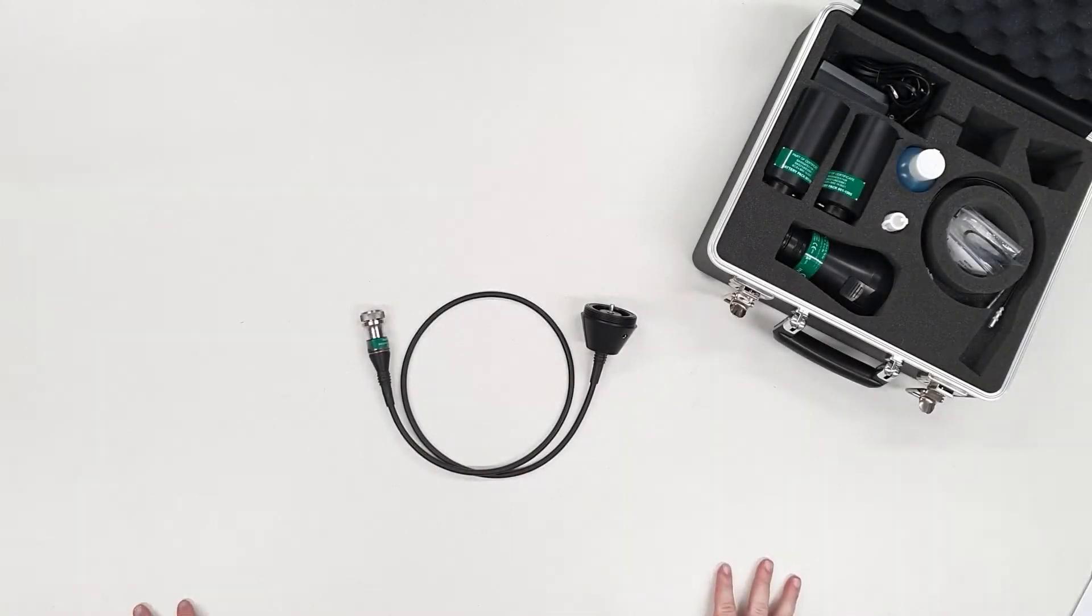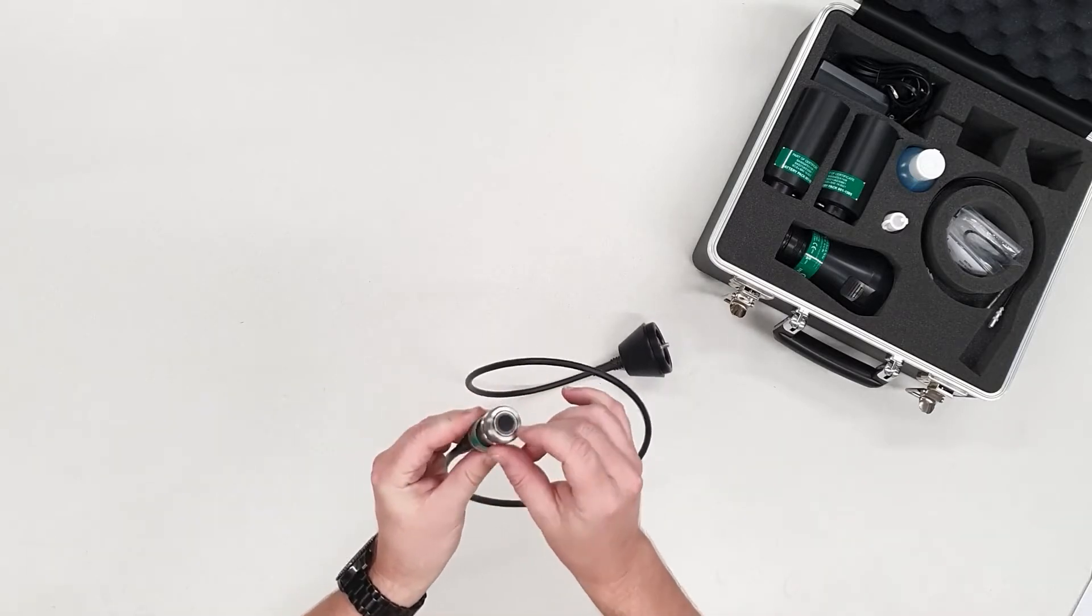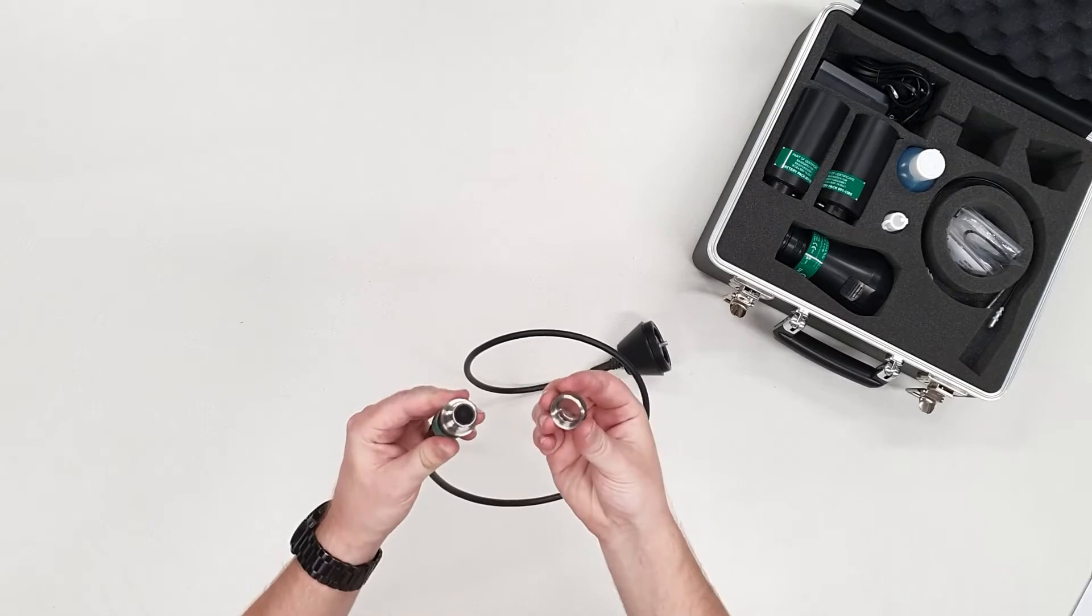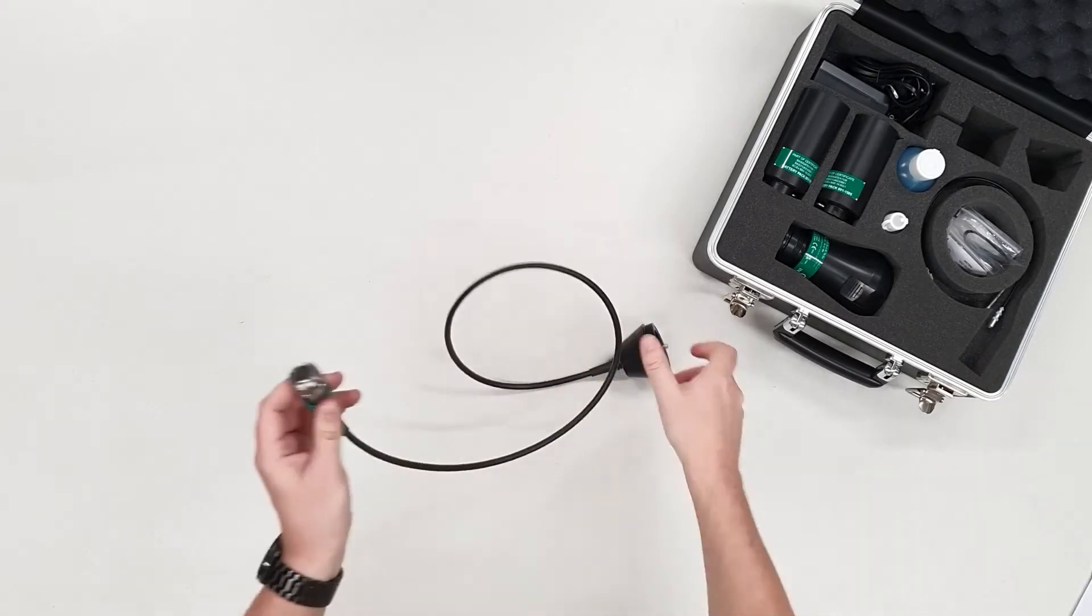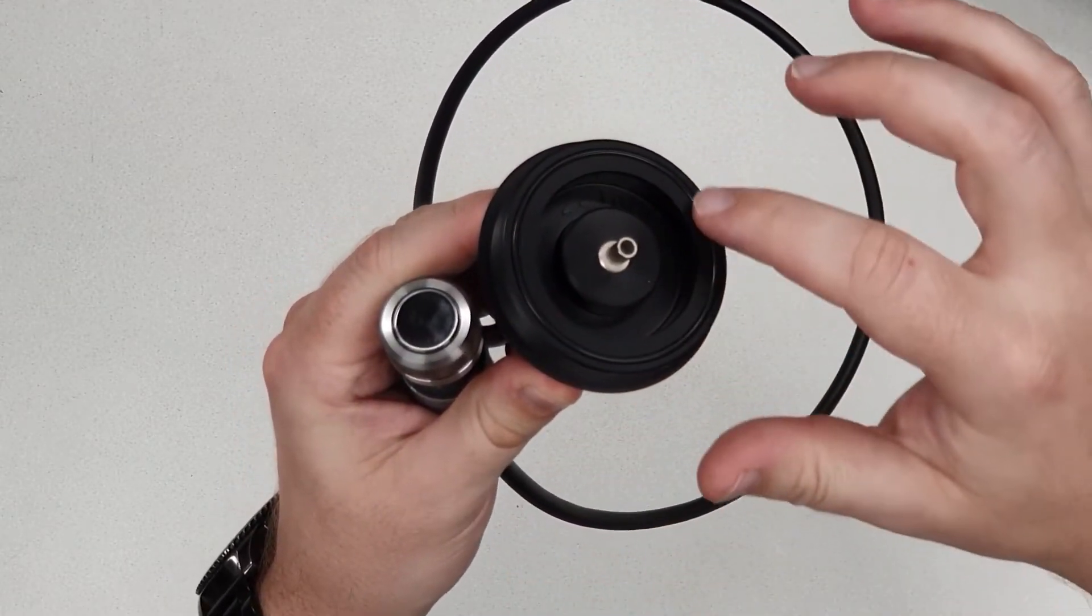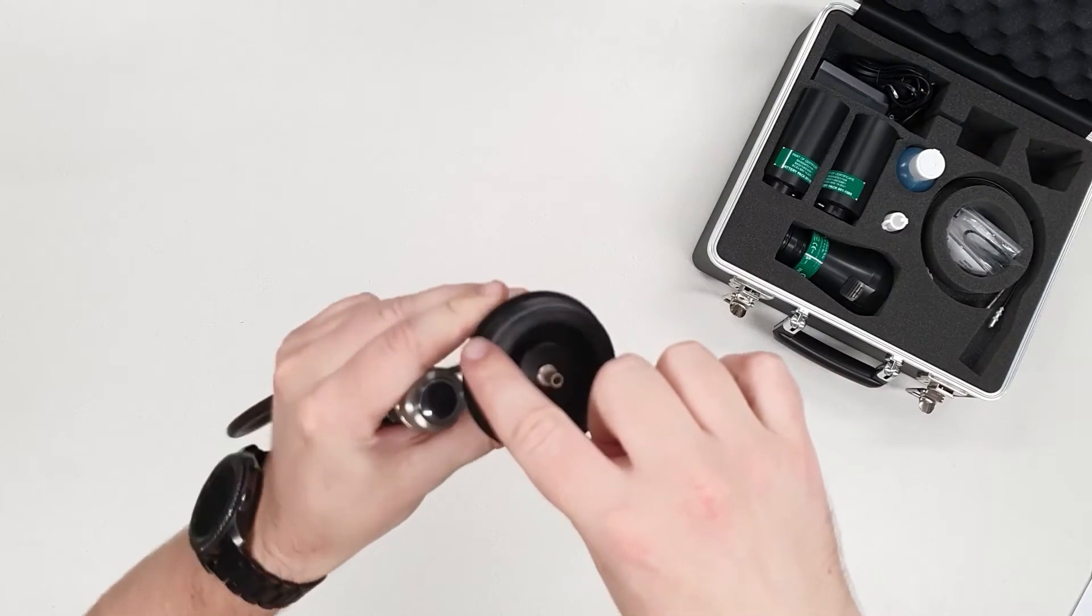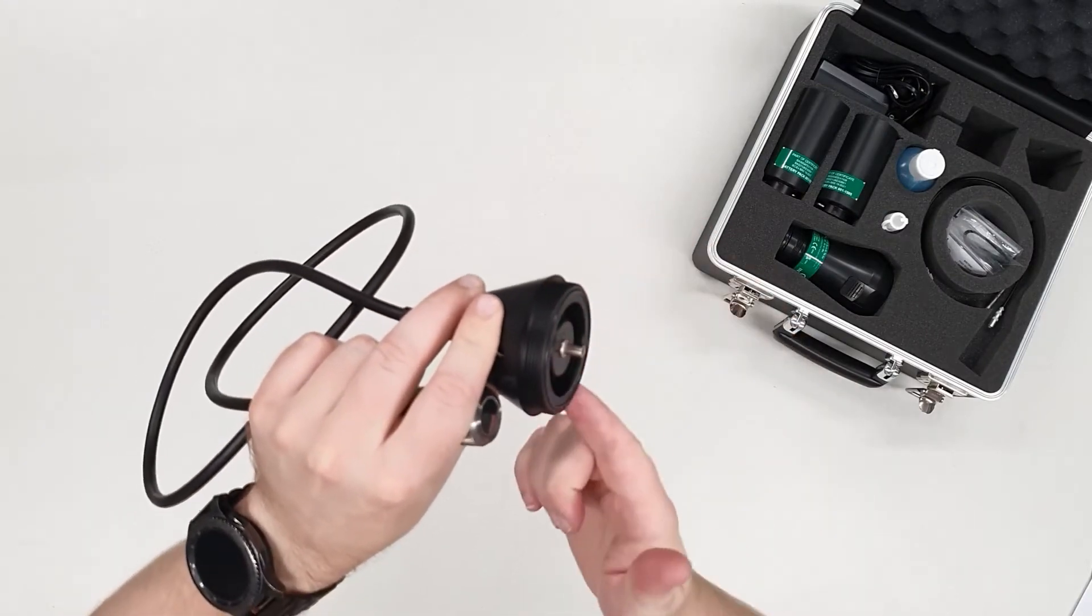Looking at the probe itself, this is the contact face. There is a protective membrane on the front here and a knurled ring holding that in place. This is the cone that connects into the main unit. There is an o-ring around here. It's very important to note the o-ring is actually on the surface here, not out here. A lot of people make that mistake.